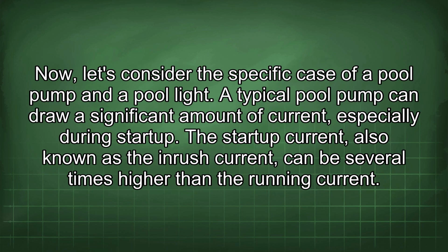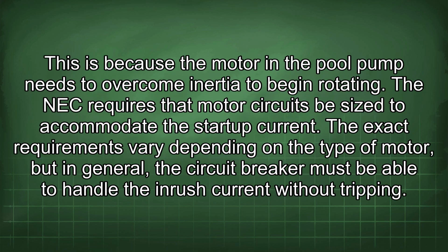Now let's consider the specific case of a pool pump and a pool light. A typical pool pump can draw a significant amount of current, especially during startup. The startup current, also known as the inrush current, can be several times higher than the running current. This is because the motor in the pool pump needs to overcome inertia to begin rotating. The NEC requires that motor circuits be sized to accommodate the startup current. The exact requirements vary depending on the type of motor, but in general, the circuit breaker must be able to handle the inrush current without tripping.